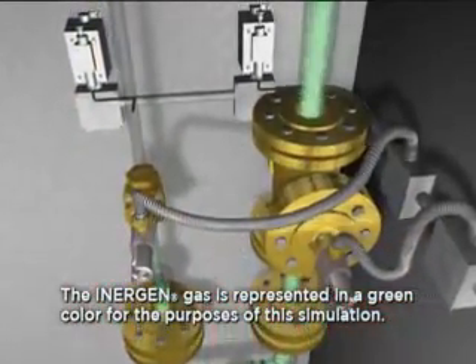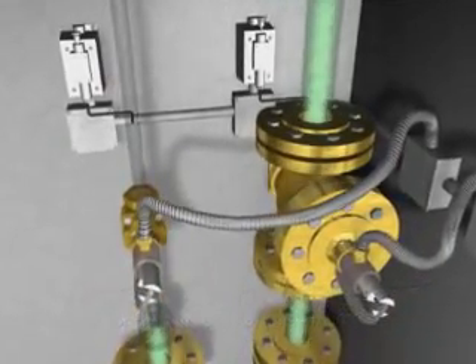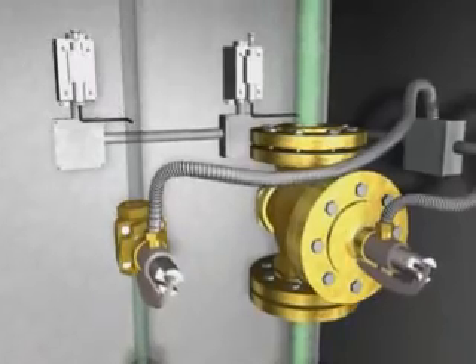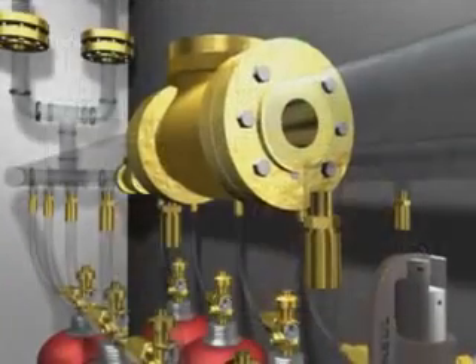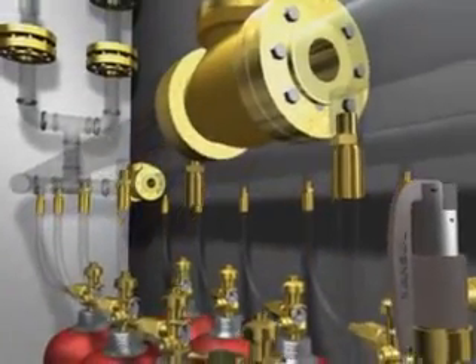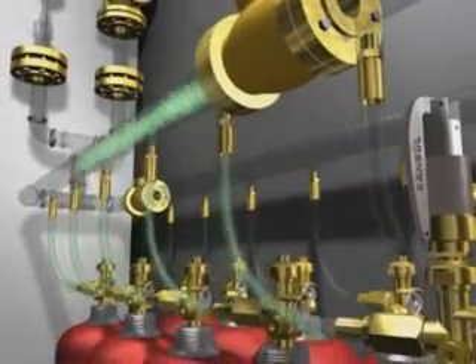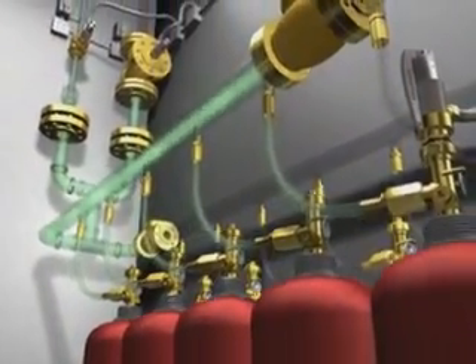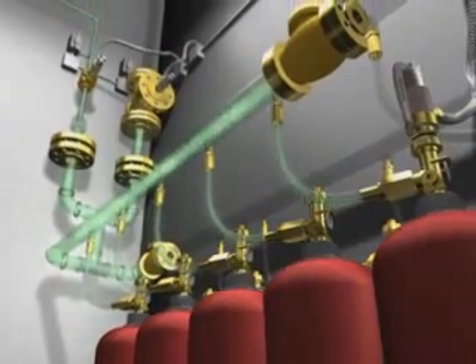In places where Inergen is protecting more than one room, a unique selector valve is used to direct the system discharge into the appropriate zone. A check valve is used in a selector valve system to separate the discharge of one zone from the other zone by preventing the Inergen flow to the main system cylinders.